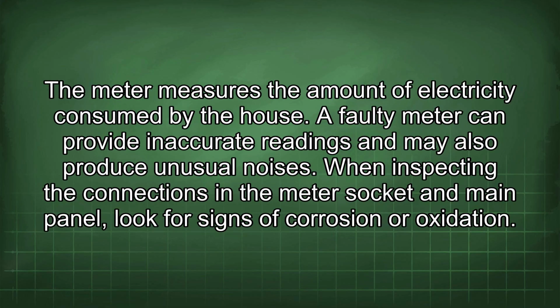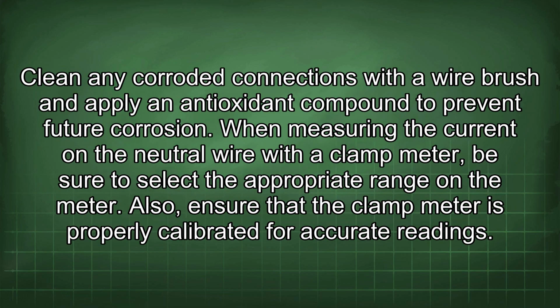The meter measures the amount of electricity consumed by the house. A faulty meter can provide inaccurate readings and may also produce unusual noises. When inspecting the connections in the meter socket and main panel, look for signs of corrosion or oxidation. Clean any corroded connections with a wire brush and apply an antioxidant compound to prevent future corrosion. When measuring the current on the neutral wire with a clamp meter, be sure to select the appropriate range on the meter. Also, ensure that the clamp meter is properly calibrated for accurate readings.